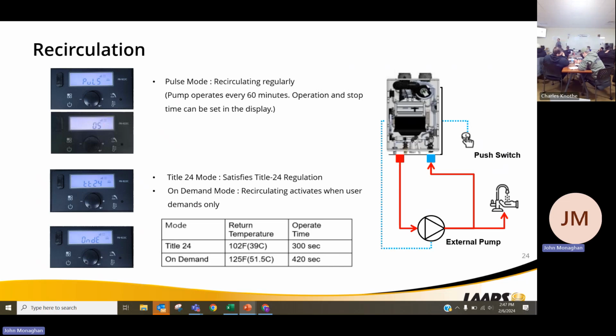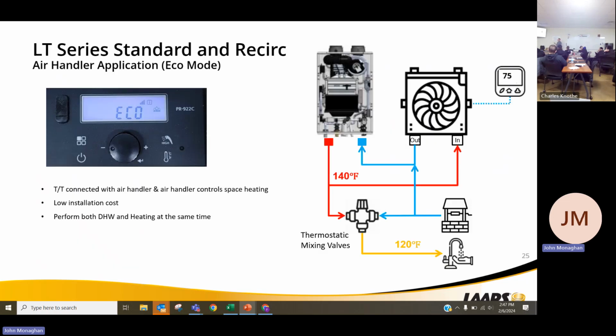So when we go through our recirculating modes, we have our pulse mode, where the recirc pump operates every 60 minutes, turning on and off. Title 24, where it turns on whenever we press the button, or on demand, whenever the user demands it. You can run it off of an aquastat as well, or your return sensor. There are some options for your DHW recirc.